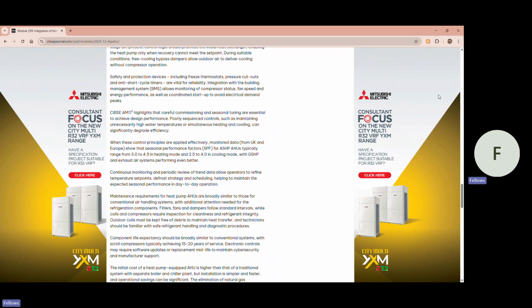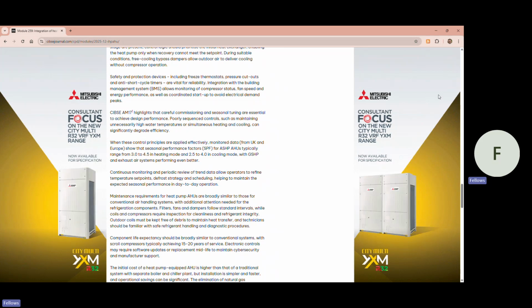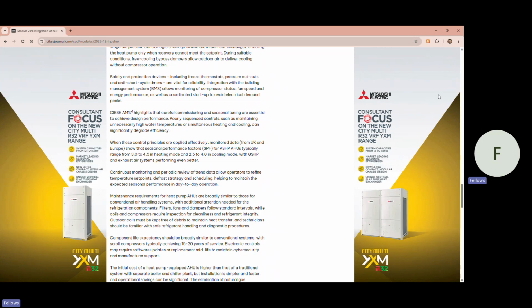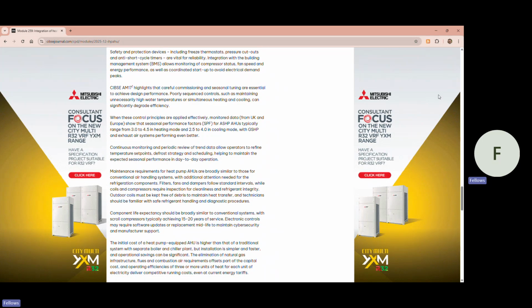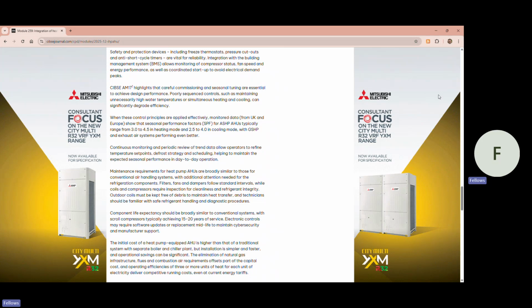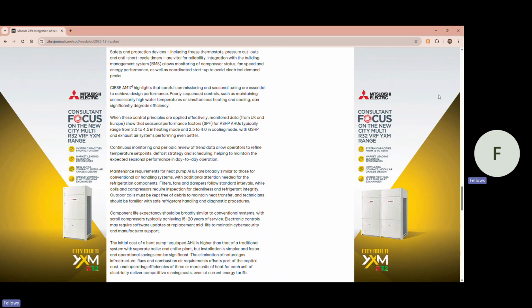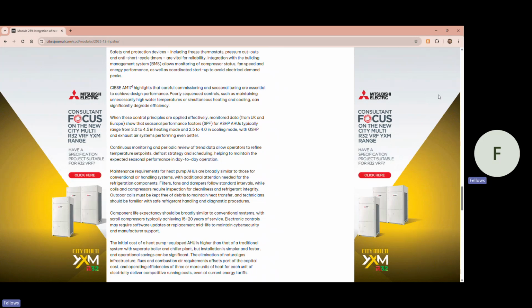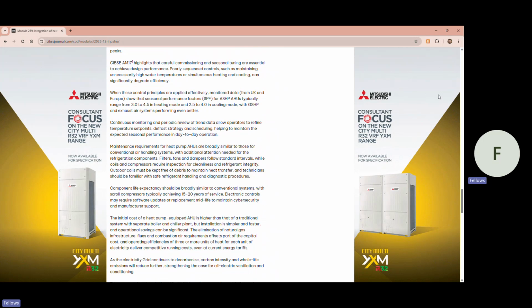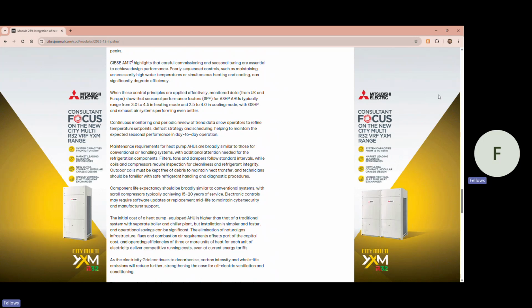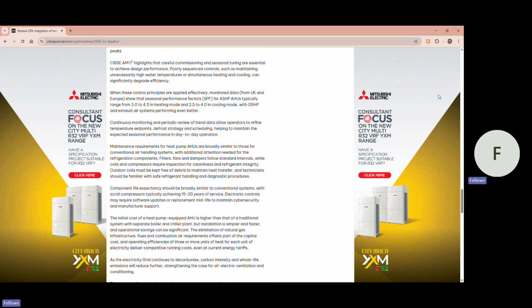Continuous monitoring and periodic review of trend data allows operators to refine temperature set points, defrost strategy, and scheduling, helping to maintain the expected seasonal performance in day-to-day operation. Maintenance requirements for heat pump AHUs are broadly similar to those for conventional air handling systems, with additional attention needed for the refrigeration components. Filters, fans, and dampers follow standard intervals, while coils and compressors require inspection for cleanliness and refrigerant integrity. Outdoor coils must be kept free of debris to maintain heat transfer, and technicians should be familiar with safe refrigerant handling and diagnostic procedures.